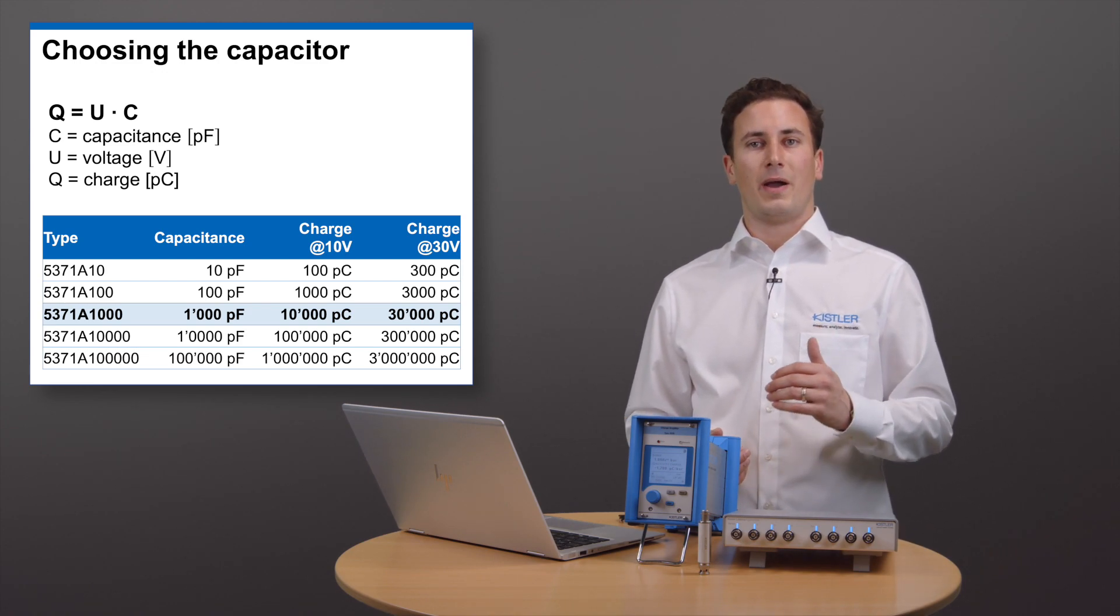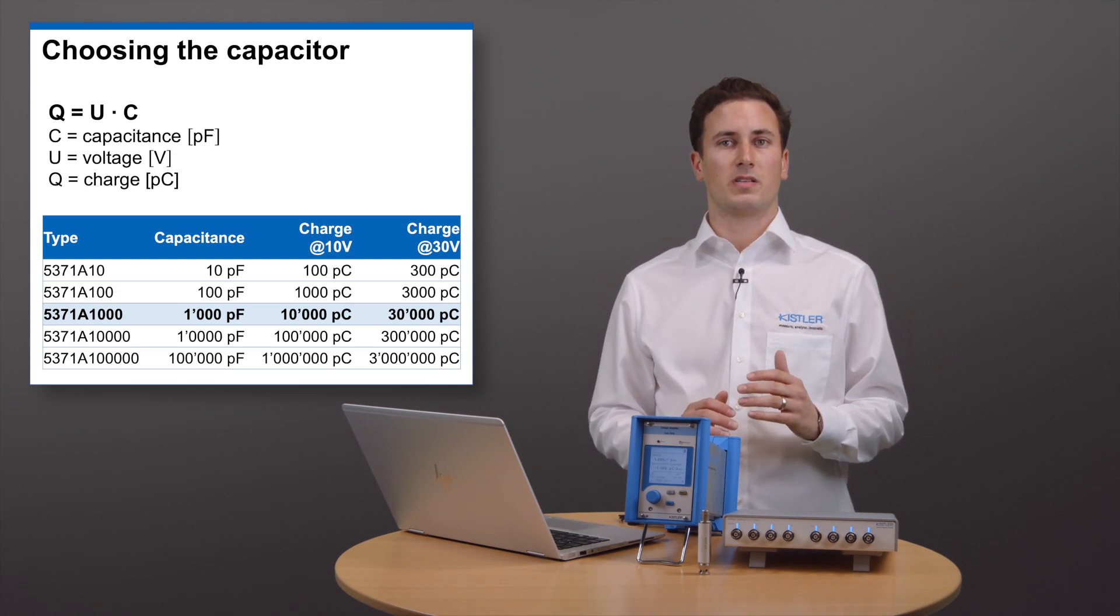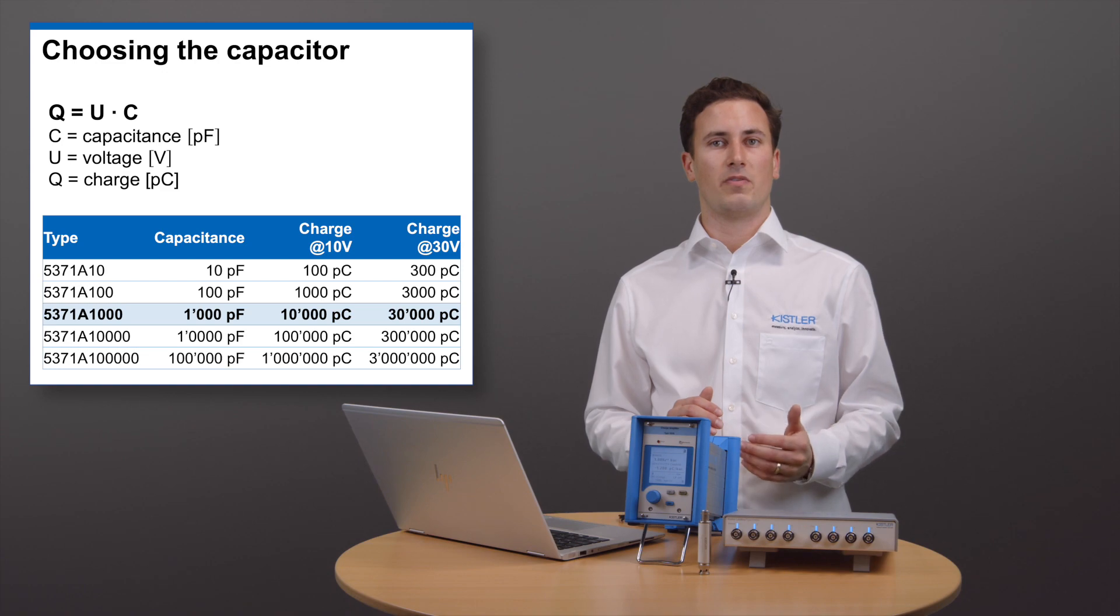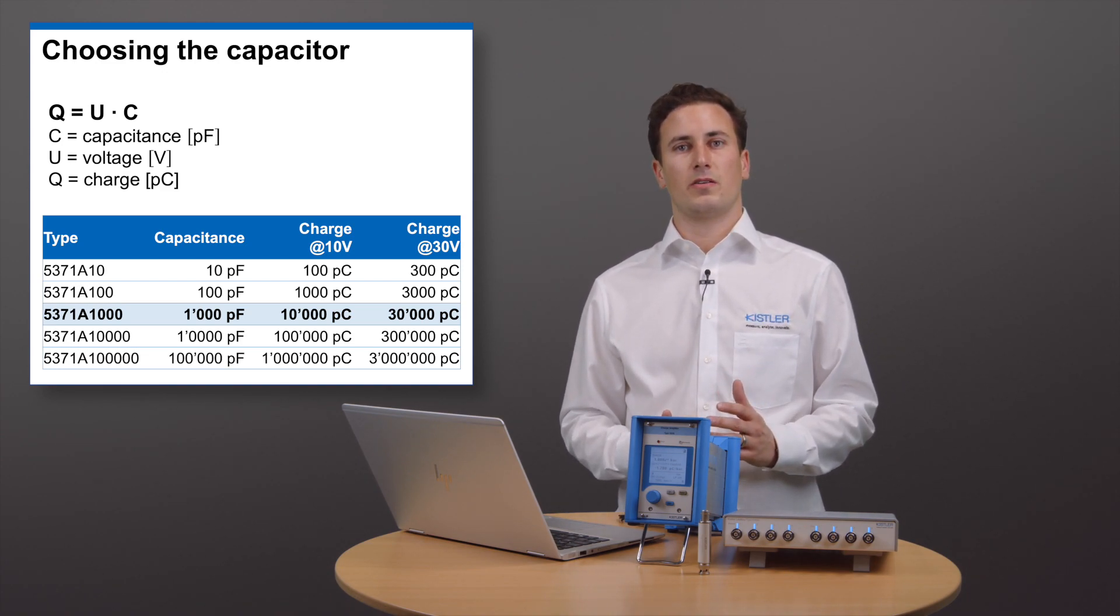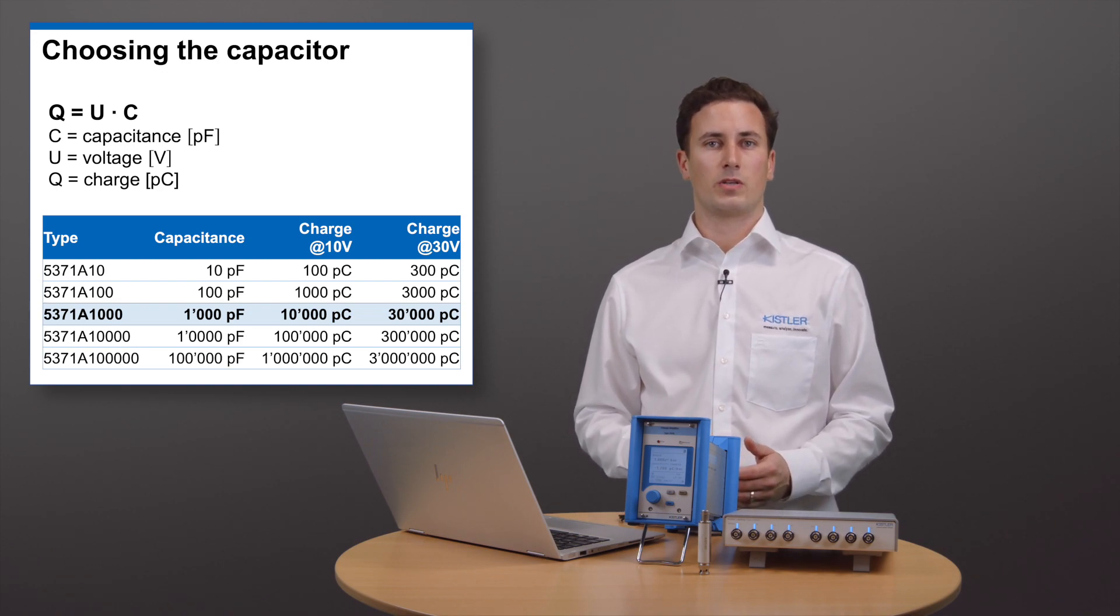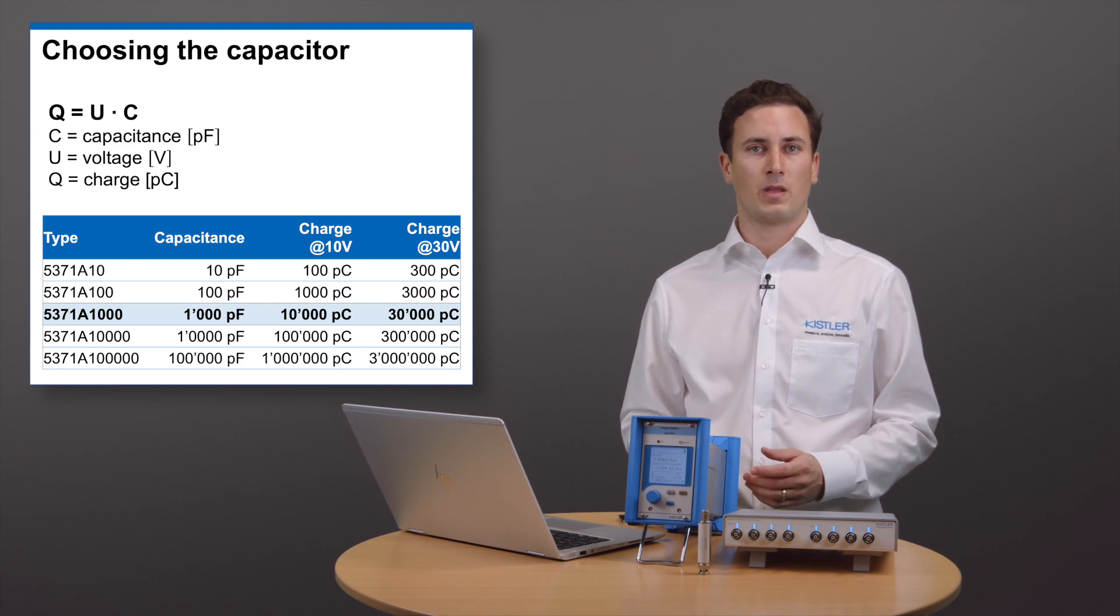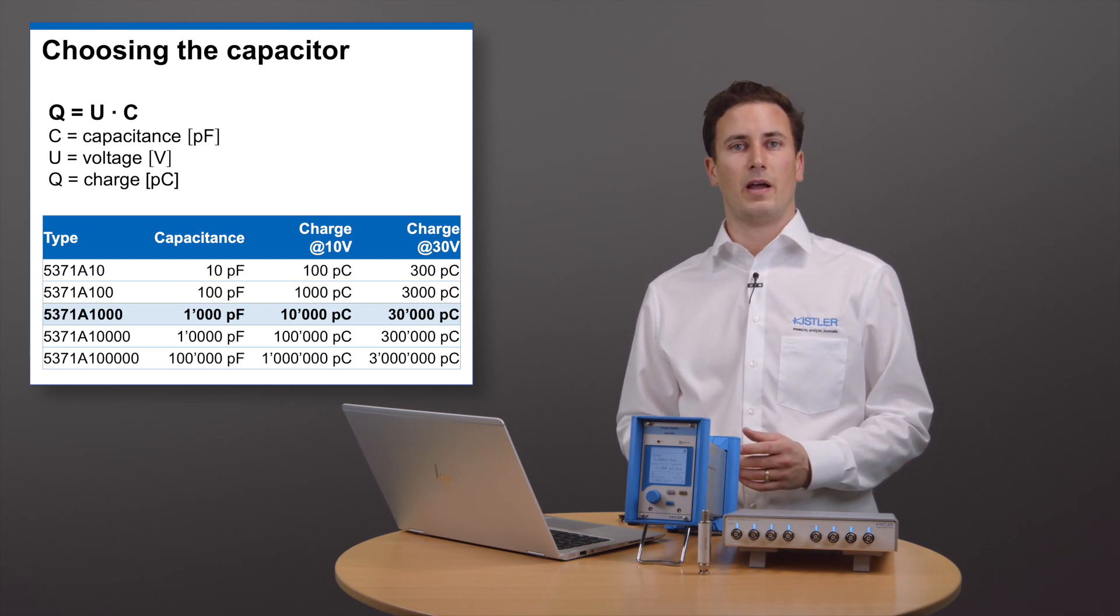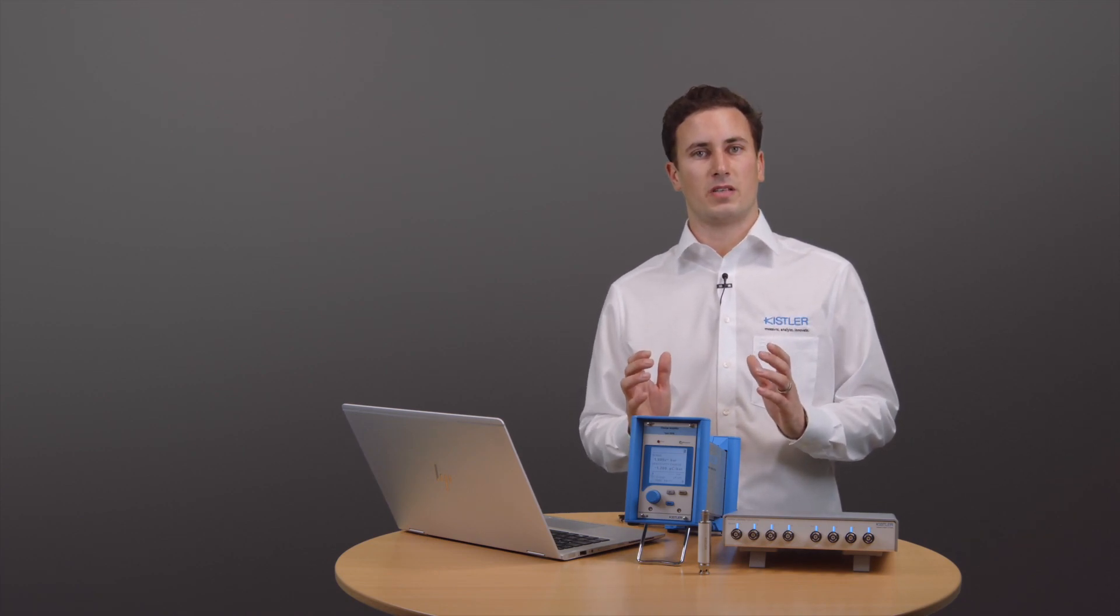I want to supply 9600 picocoulomb to simulate my sensor. The capacitor is limited to 30V, but this is no problem since we are using our lab amp as a source which can provide up to 10V. The next available capacitor is the 1000 picofarad version, which will allow me to supply up to 10,000 picocoulomb. With this capacitor, I will need 9.6V to supply 9600 picocoulomb.